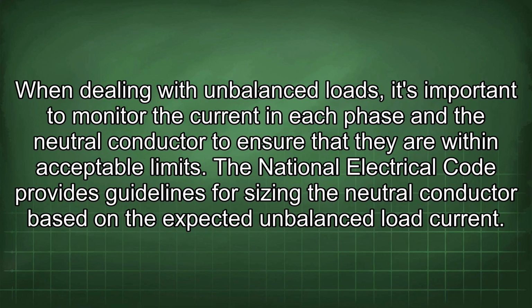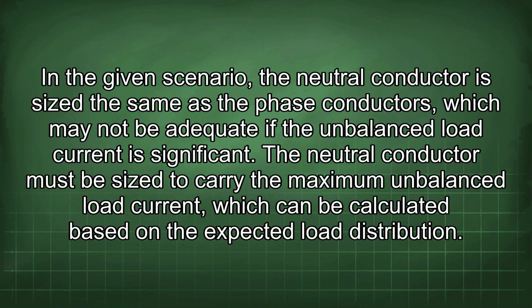When dealing with unbalanced loads, it's important to monitor the current in each phase and the neutral conductor to ensure that they are within acceptable limits. The National Electrical Code provides guidelines for sizing the neutral conductor based on the expected unbalanced load current. In the given scenario, the neutral conductor is sized the same as the phase conductors, which may not be adequate if the unbalanced load current is significant.